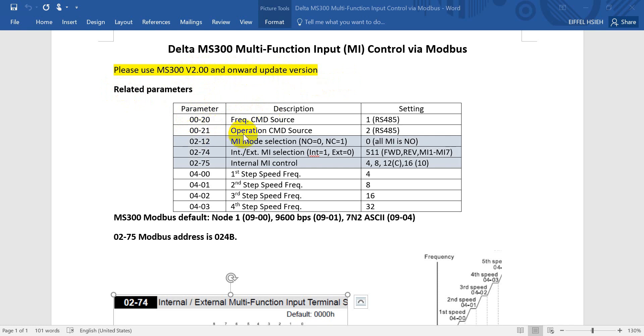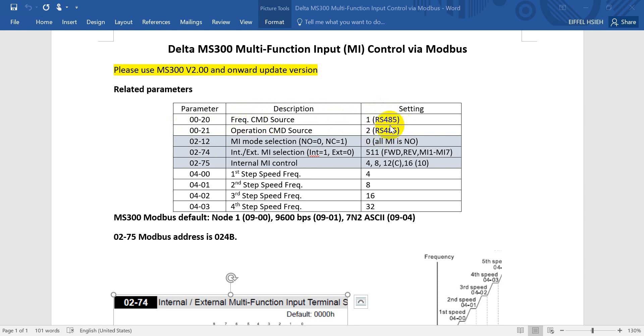The operation command source are P00-20 and P00-21. Here we should set to 1 and 2. That means RS-485. And actually for P00-21 you can also use other functions, but for the frequency command P00-20 you must set to RS-485.